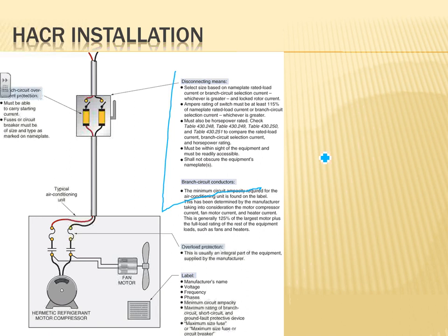But when it comes to disconnects, there are two types of disconnect: fuseless disconnect, and fused disconnect, a fuse inside the disconnect. If you put a fuse in a disconnect, then your sizing will all get screwed up. Just to give you an idea, the way we size the fuse, you might end up with a 60 amp fuse, and based on the NEC code book, a 30 amp disconnect. So either you have a fuse holder right underneath it to fit the 60 amp fuse, or if you want to put a 60 amp fuse in a packaged fuse holder with a disconnect, the disconnect has to be rated for 60. My point is, you might have to up your disconnect if you're using a fuse inside it, based on the size of your fuse.